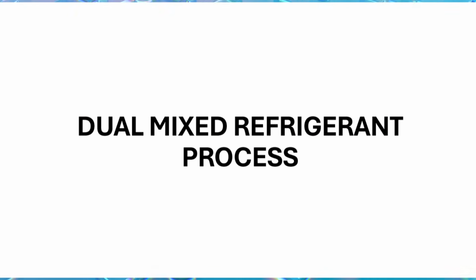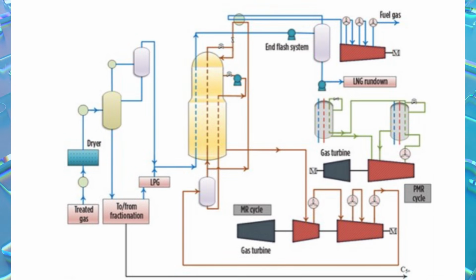The dual mixed refrigerant DMR process has been used for train capacities averaging 4.8 MTPY. The process configuration is similar to the propane pre-cooled mixed refrigerant process, with pre-cooling requiring a mixture of ethane and propane rather than pure propane. SWHEs are used for pre-cooling. Frame 7 gas turbines are responsible for driving the refrigerant and axial compressors. For compression of cold refrigerant, axial compressors are used during the compression stages.